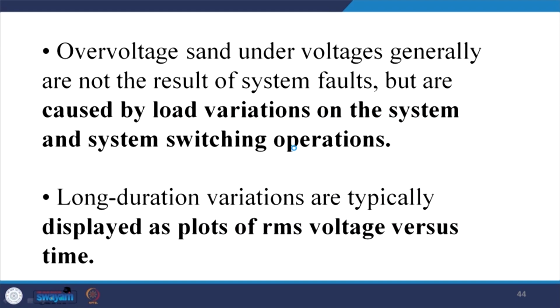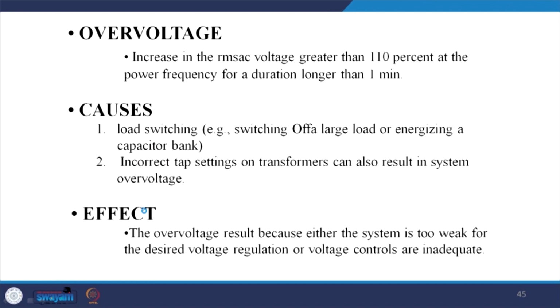Over voltages and under voltages are generally not the result of system faults, but are caused by load variations in the system, such as switching operations. Long duration variations are typically displayed as a plot of RMS voltage versus time. I can show you in the next few figures.